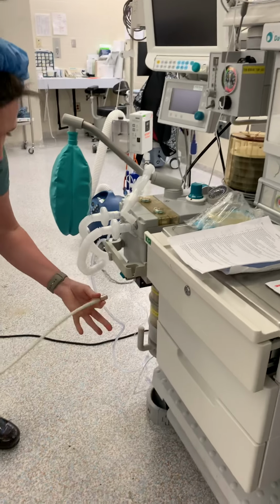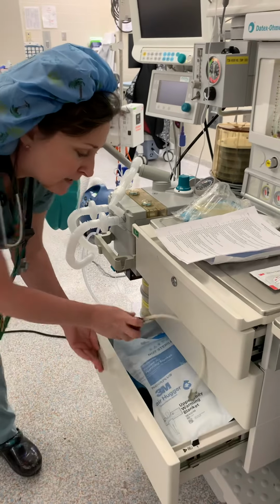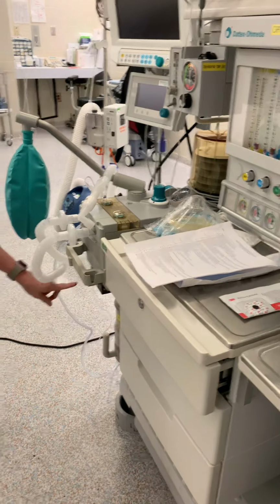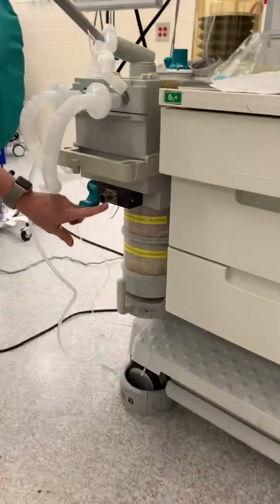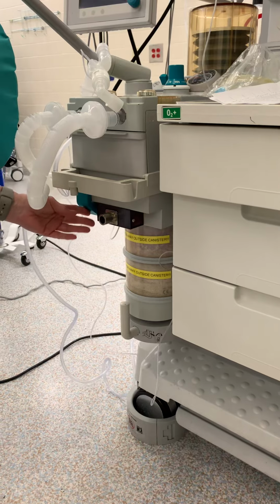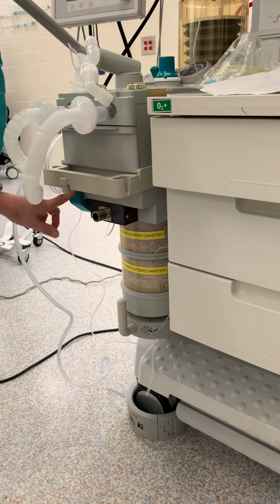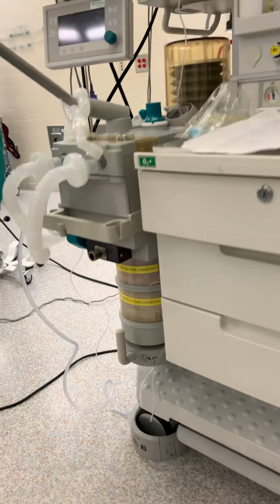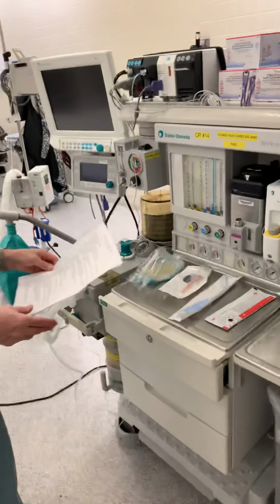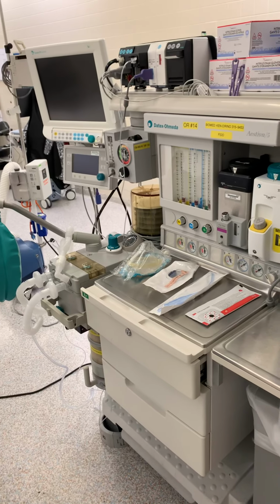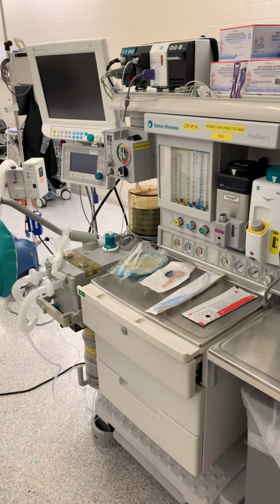Just disconnect by pulling, put your bulb back in your drawer. Very important step to switch back from the common gas outlet back to the machine. That switch is important to make sure your machine is functional. Now, let's move on to test the high pressure system.